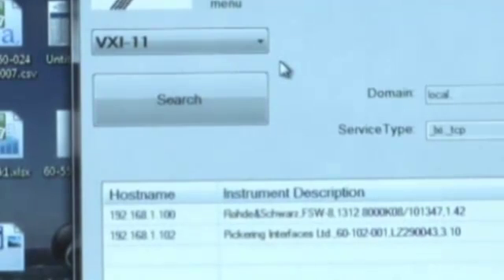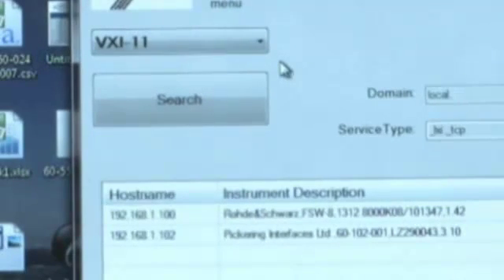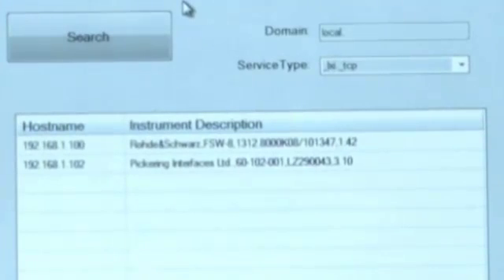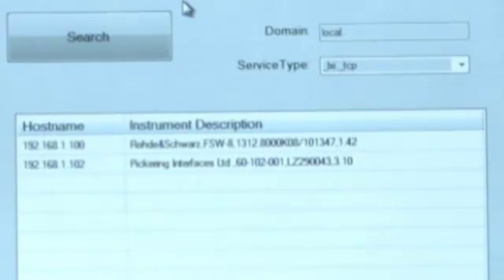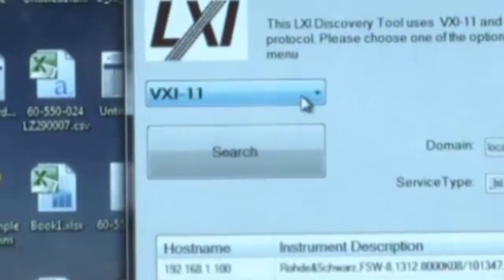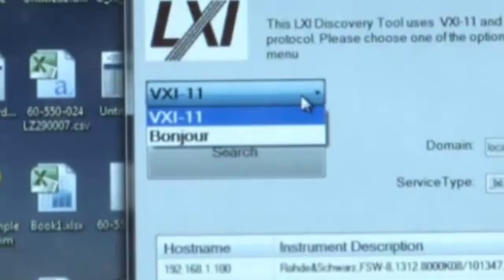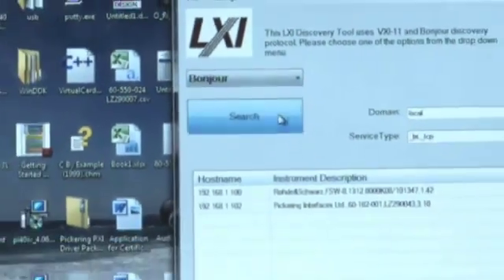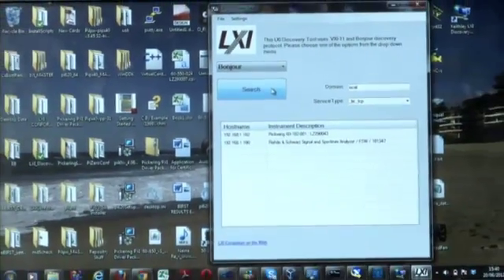As you can see, the tool has discovered two LXI products: Rohde & Schwarz Spectrum Analyzer and Pickering Interfaces Modular Chassis. You can alternately discover via Bonjour which uses MDNS and discover over Multicast.